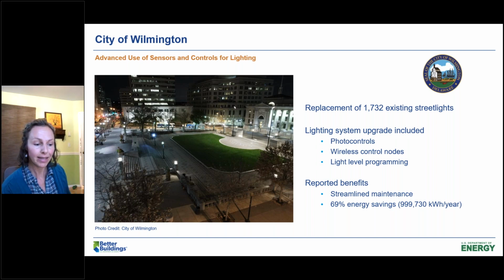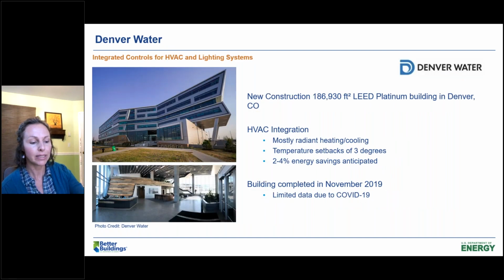savings. And on the next slide, I'd like to talk about Denver Water's newly constructed LEED Platinum building in Denver, Colorado. The building has a networked lighting control system that is BACnet integrated with the building management system, and that allows for real-time occupancy data to modify the settings for their mostly radiant heating and cooling system. They implemented temperature setbacks of 3 degrees, which they are anticipating will save 2 to 4% above a system that is not integrated. The estimates for this building are based on design documents, efficiency studies, and energy modeling, as the building had very limited use after being completed and occupied in late 2019. And this site was recognized under our integrated controls for HVAC and lighting category.